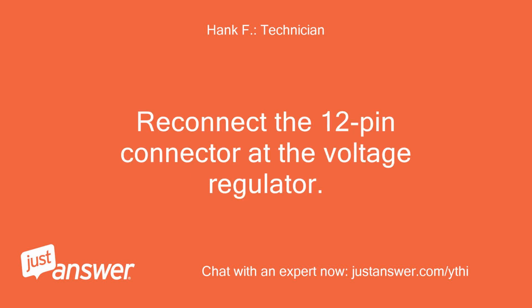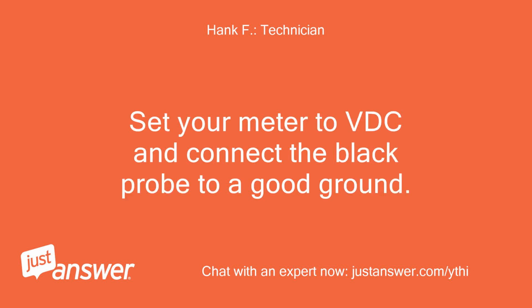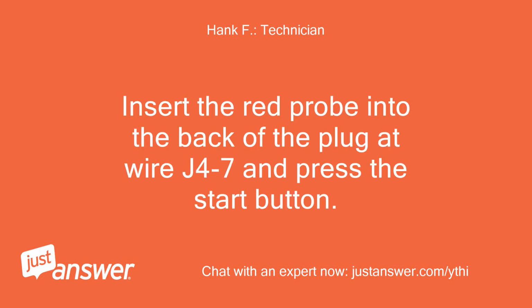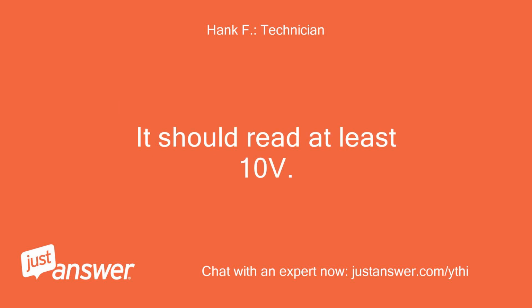Reconnect the 12-pin connector at the voltage regulator. Set your meter to VDC and connect the black probe to a good ground. Insert the red probe into the back of the plug at wire J4-7 and press the start button. It should read at least 10 volts.